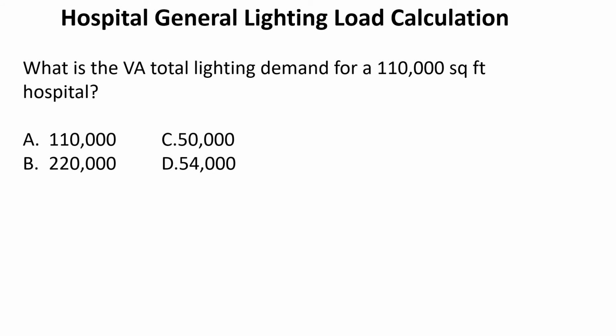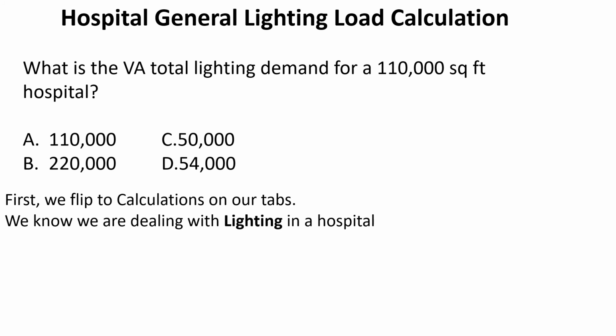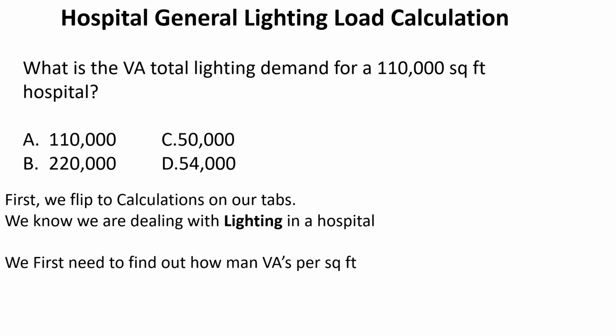Okay, let's do a hospital general lighting load calculation. What is the VA lighting demand for a 110,000 square foot hospital? Okay, so we have some options. Nothing really stands out right away. First, we're going to flip to our calculations tab on our codebook.